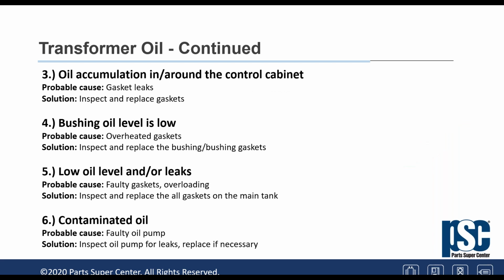Oil accumulation around the control cabinet. Well, that's the beauty about transformers. If there's a leak, we've got to find it on the pad, and the inspection of the transformer tells us something is happening here. So where is the oil coming from? It could be, of course, gasket leaks, or maybe too much pressure on the oil in the transformer that pushes the oil through the gaskets. And again, we have to inspect and replace the gaskets if it's the gasket.